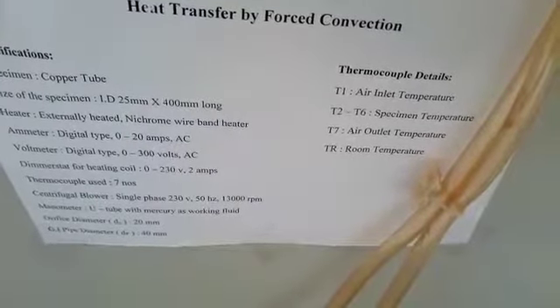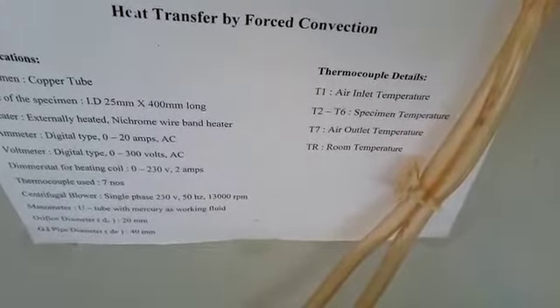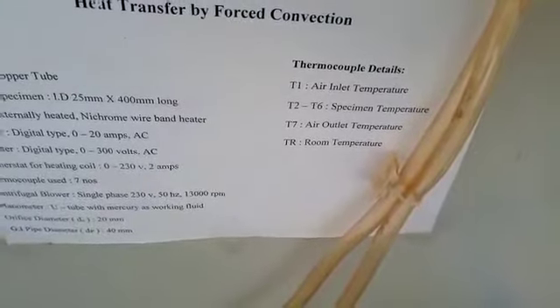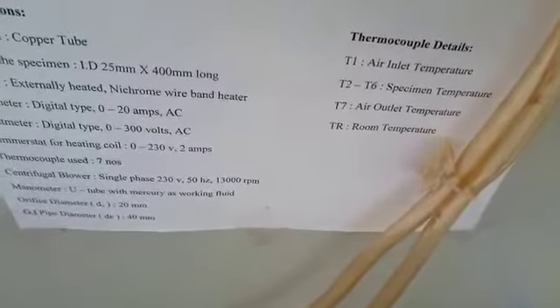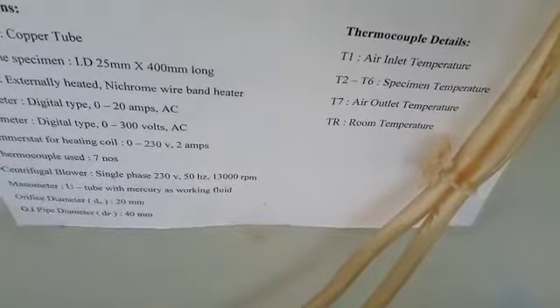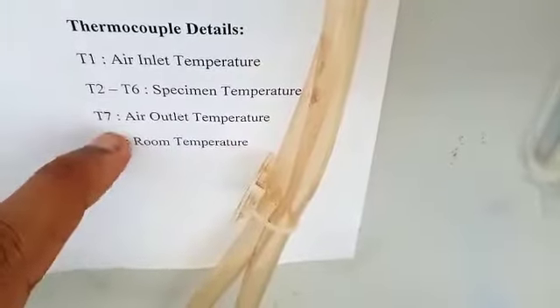The dimmerstat for the heating coil is 0 to 230 volt and 2 amps. Seven thermocouples are used. The centrifugal blower is single phase, 230 volt, 50 Hz, at 13000 rpm. The manometer is a U-tube type with mercury as working fluid. The orifice diameter D₀ is 20 mm and GI pipe diameter Dₚ is 40 mm. T1 is air inlet temperature, T2 to T6 are specimen temperatures, T7 is air outlet temperature, and Tr is room temperature.